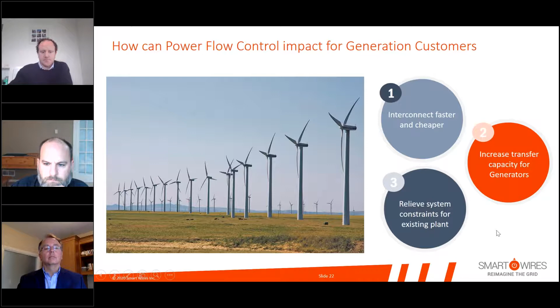UK Power Networks is an example of a distribution customer in the UK that's using this modular flow controller, optimized across two different circuits, to balance out power flows in real time and allow unconstrained generation export on their distribution network. In this case, UKPN was looking at building new circuits or reconductoring circuits to facilitate new generation and demand requests that they were receiving.